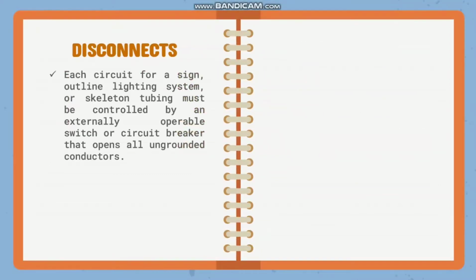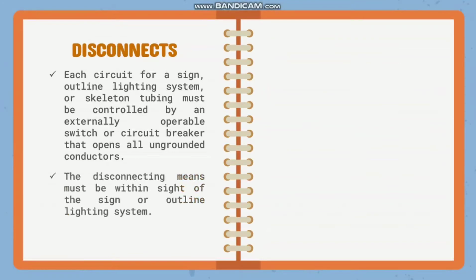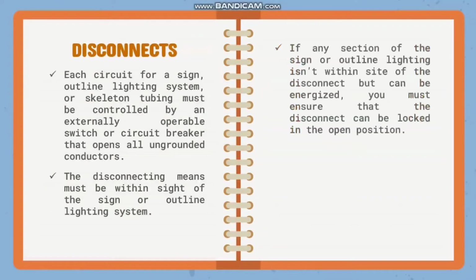For disconnects, each circuit for a sign outline lighting system or skeleton tubing must be controlled by an externally operable switch or circuit breaker that opens all ungrounded conductors. The disconnecting means must be within sight of the sign or outline lighting system. So, ibig sabihin, dapat yung disconnecting means tulad ng circuit breaker or fuse switch ng sign or outline lighting system is dapat within the line of sight or nakikita. So, visible and not more than 50 feet distant from each other.